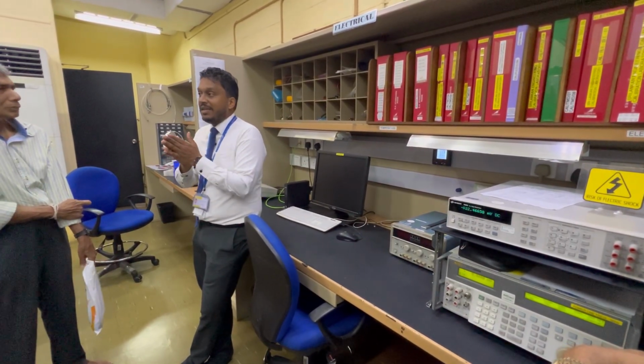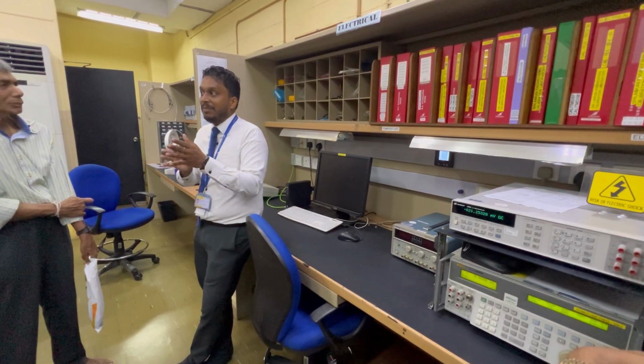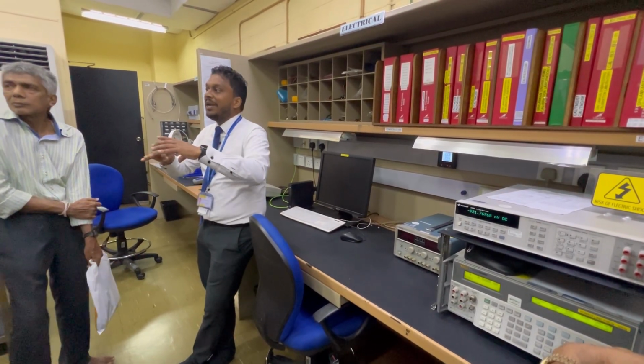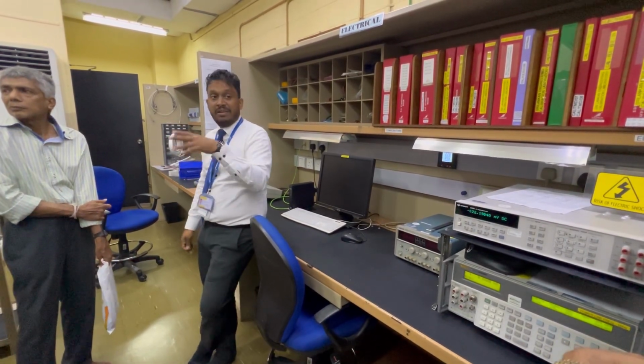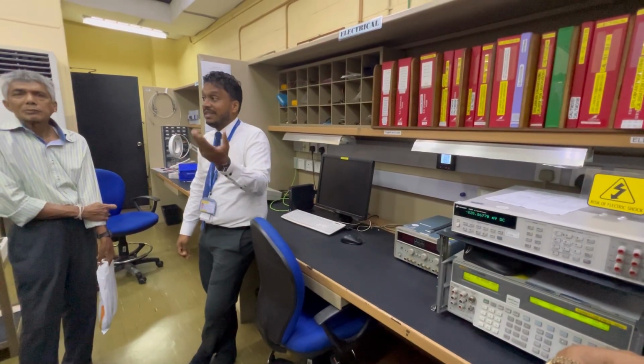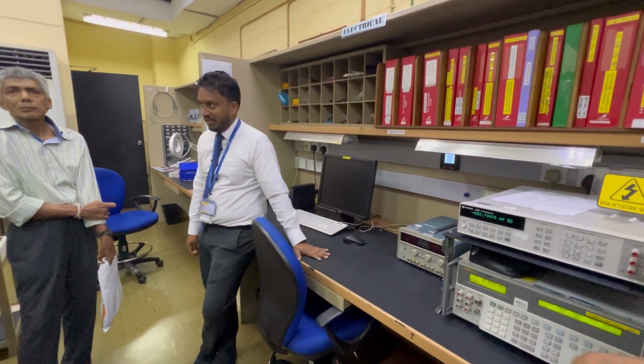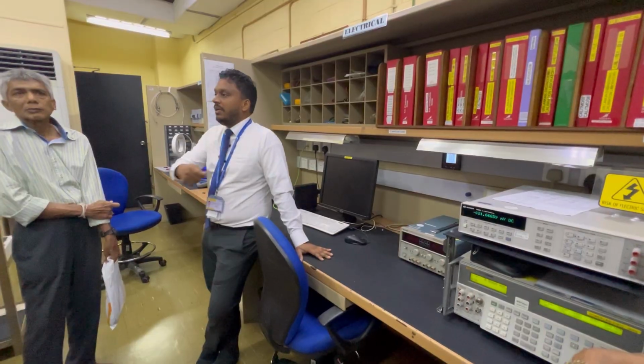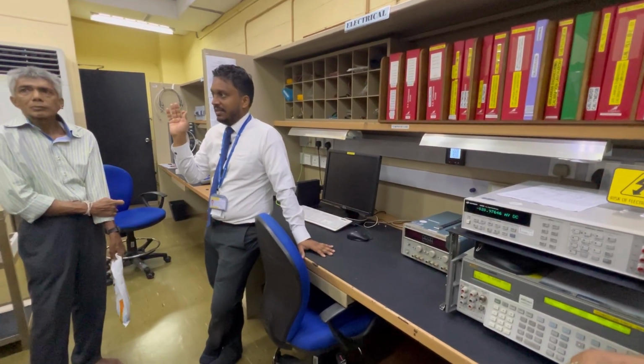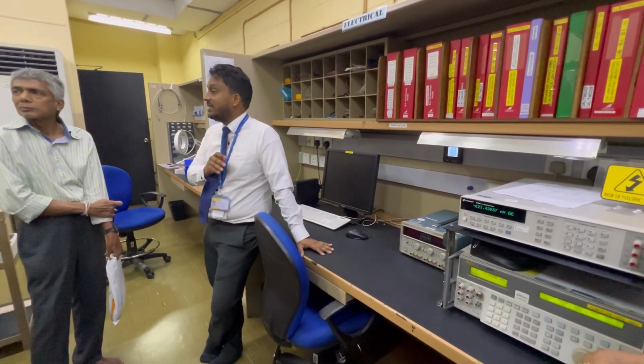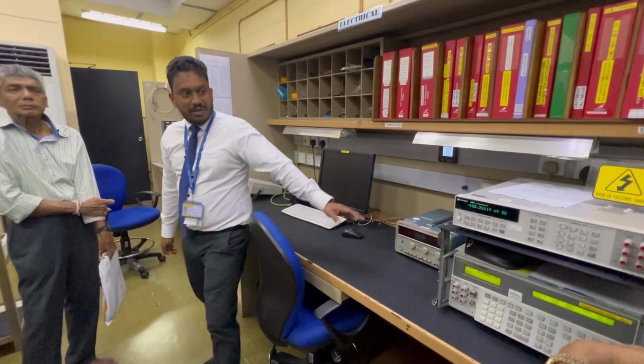That's why some laboratories tend to keep your calibration intervals to like 2 years. Because an accredited laboratory, if the customer proves that your reference is wrong, you have to recall all your calibration certificates and then do a free calibration, which is extremely costly.